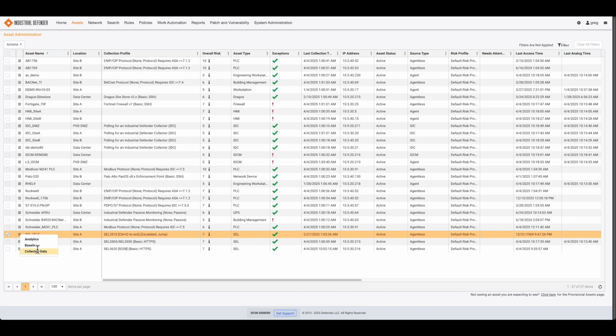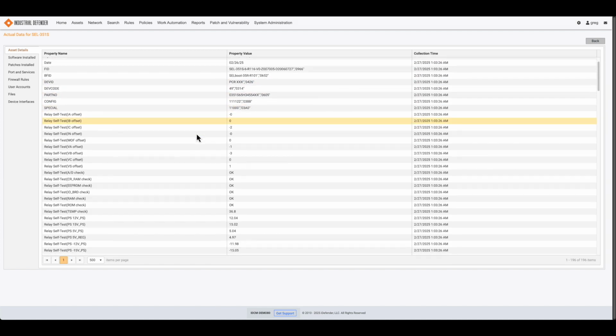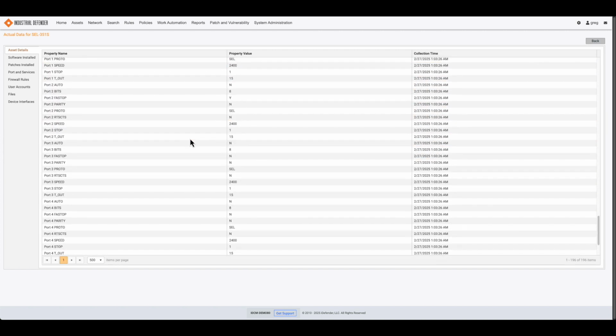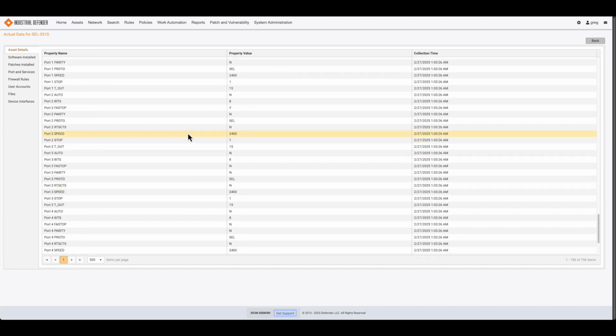What we're doing to connect and collect this data from this relay is we are, via the IP network, SSHing to the RTAC, the 3530, and then from the 3530, using that as a jump box to then connect through the serial cable to the relay behind the RTAC. So all of this data we're collecting to monitor this relay, we're connecting through the serial cable connection.